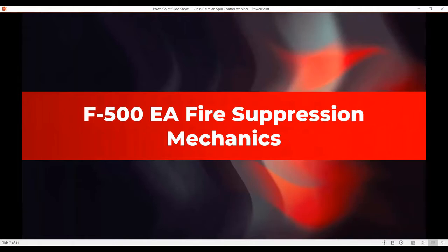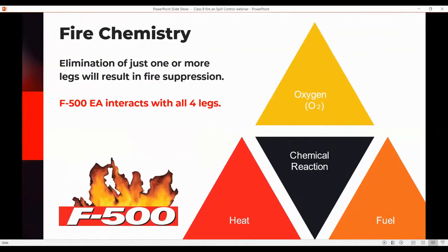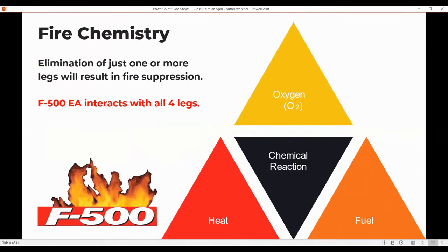Now let's go through the fire suppression mechanics of what that F500 molecule in the water can do for you. Looking at basic fire chemistry, we know from essentials of firefighting about the fire tetrahedron. If you remove any one leg, the fire goes out. Using plain water, you're attacking the heat leg. Using a foam, you're putting a blanket between the fuel and the oxygen, separating them mechanically. Using a dry chemical extinguisher, you're interrupting the free radical chain reaction. Each of those works on one leg of the fire tetrahedron.